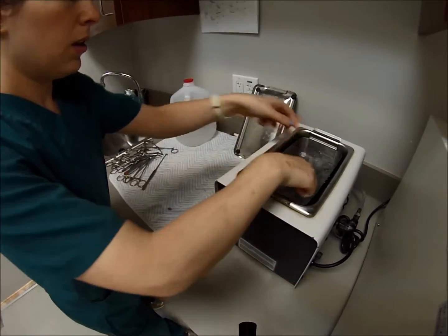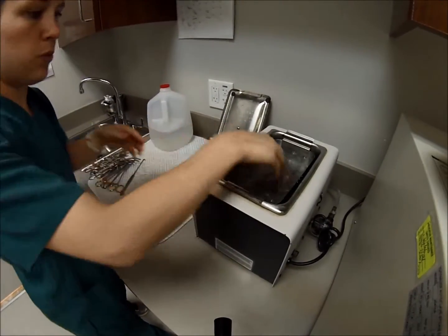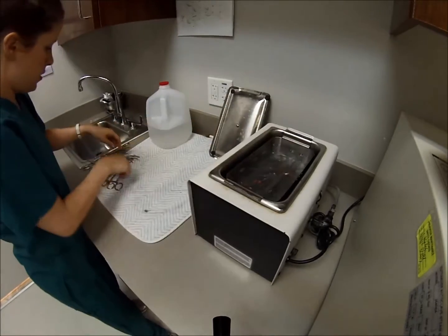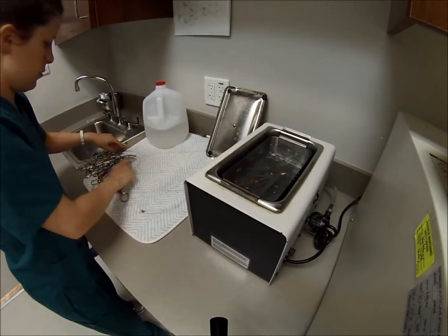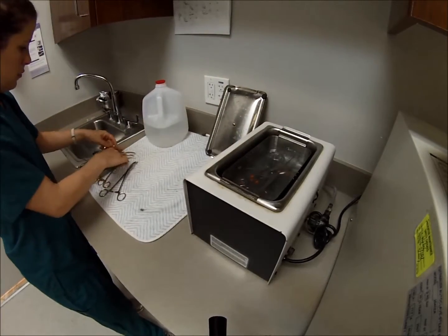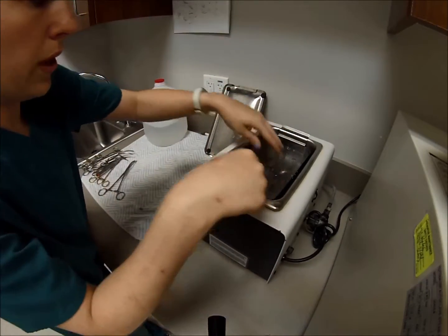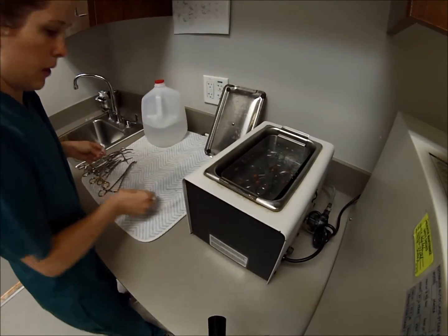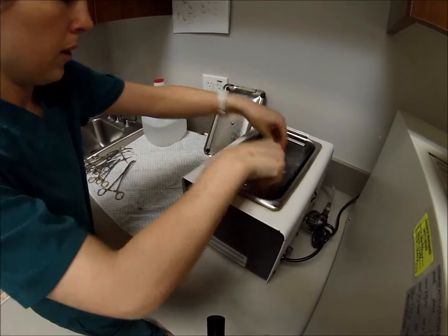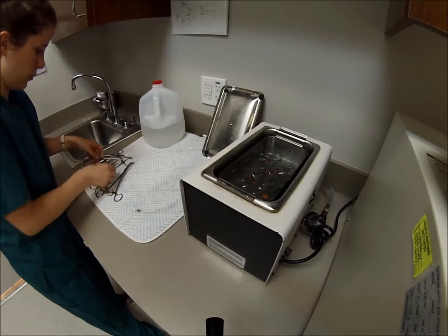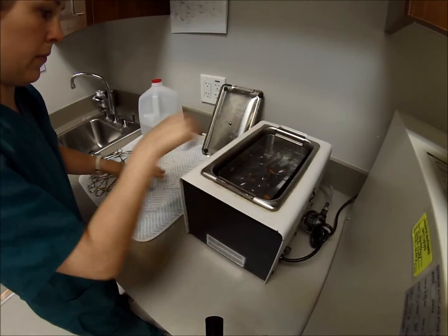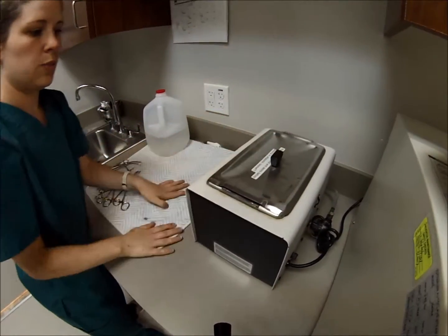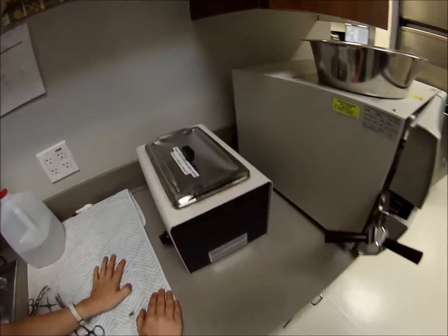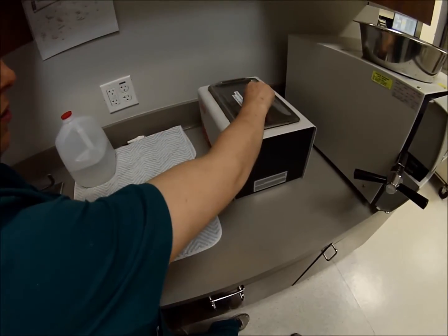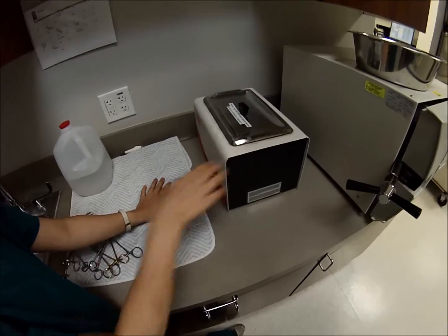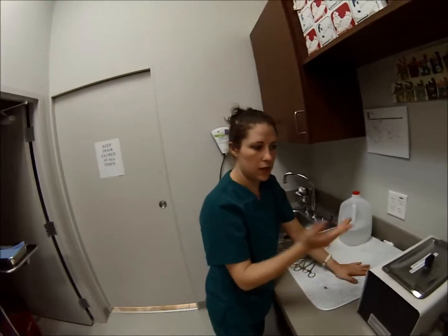The enzymatic cleaner that's in here is mixed with distilled water per the instructions on the bottle. Give that a second. Once these are loaded, I don't want to load it too heavily because I want to make sure that there's enough room for the bubbles to clean around each instrument. So I might do 2 loads. Okay. Now put the lid on, and this, per the instructions on the bottle, runs for about 10 minutes. So I'll go ahead and set my timer. 10 minutes, and that will run, and I will take them out when they're finished.